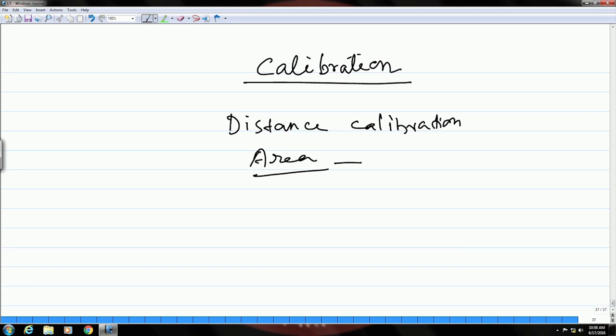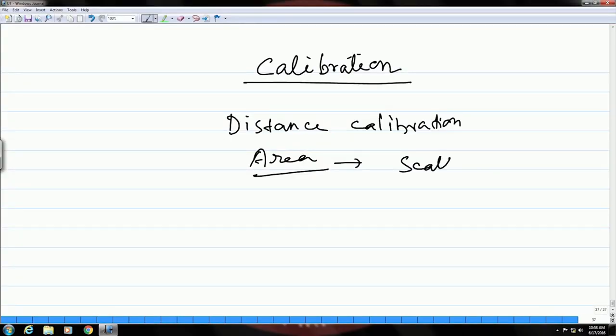Why area? Because the intensity of the echo depends on the scattering area, or the area of the interface, or the area of the defect which is scattering it. Okay. So therefore, the area also has to be calibrated so that you would be able to get some idea as to how big the defect is, whether it is a big defect or a small defect. So in order to do that, you need to calibrate the instrument for area also.